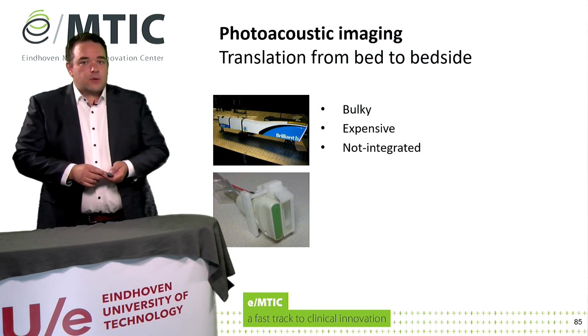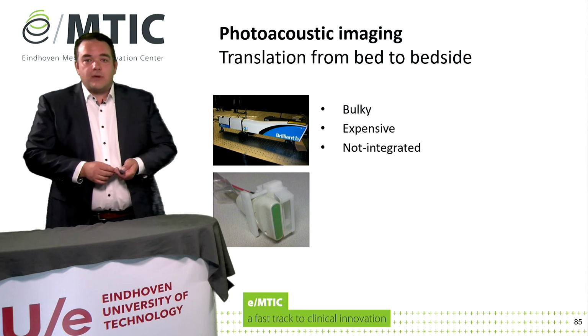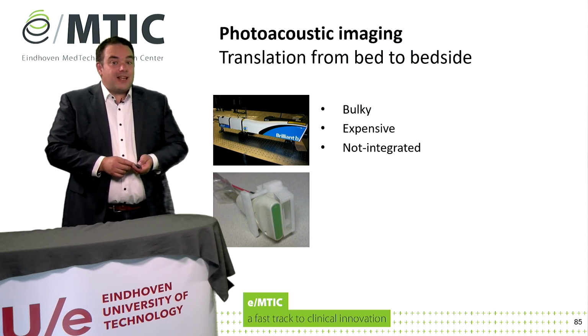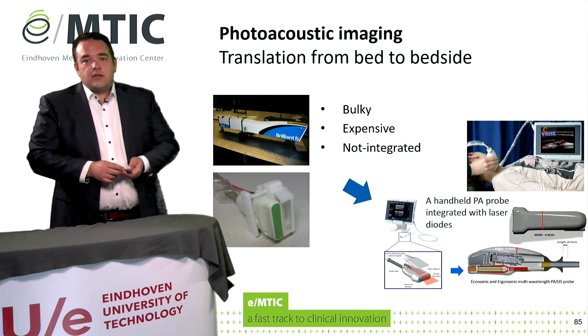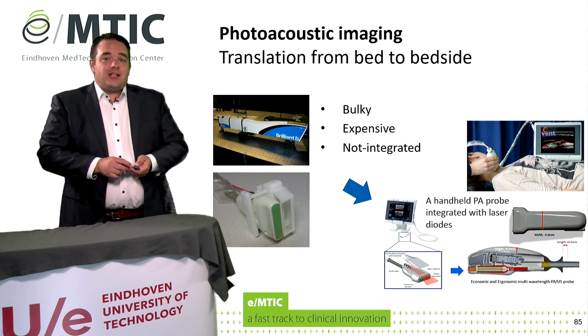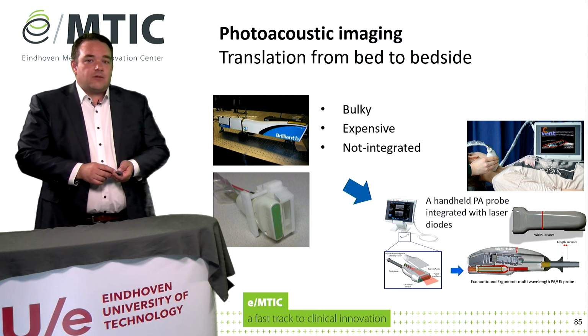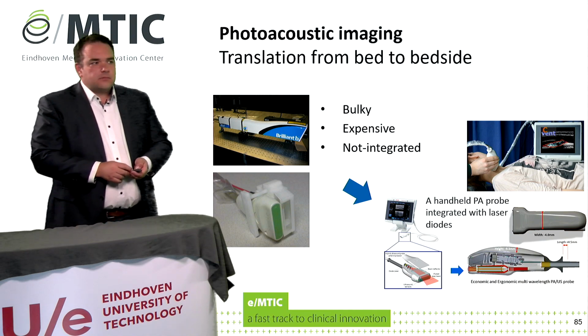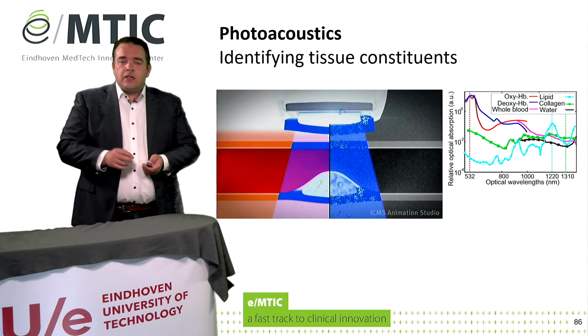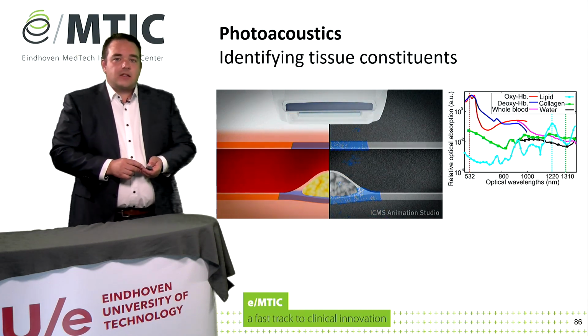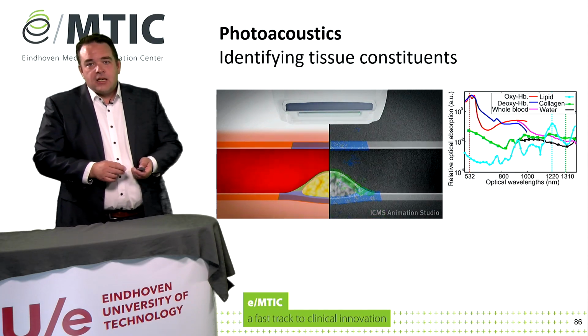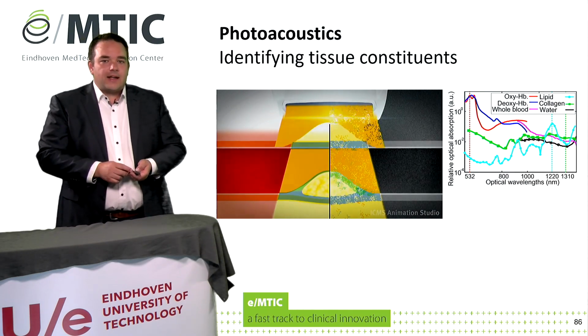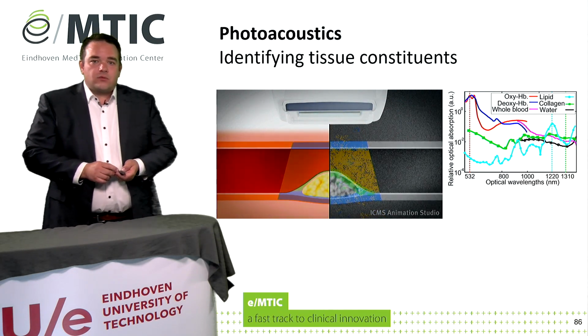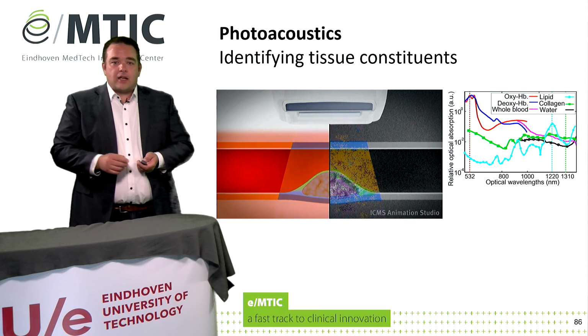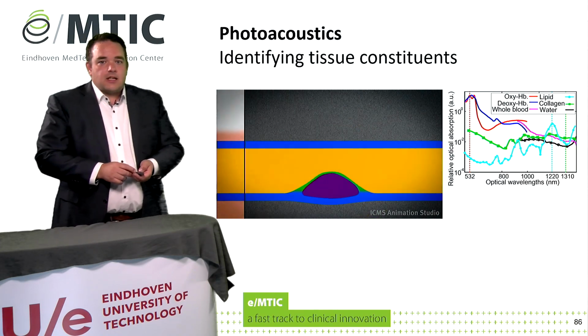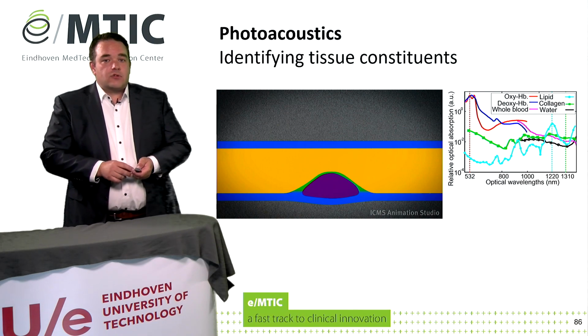However, to go into the clinic, where it's not widely applied yet, we need to get away from these bulky and expensive lasers that we typically use and are also typically not integrated with the ultrasound device. So recently we see a lot of developments where new handheld systems are being developed with the optics integrated with the ultrasonics. And when we have these devices and we choose our wavelengths of light wisely, we can actually perform non-invasive spectroscopy with photoacoustics. So we can send out different pulses with different wavelengths, get the received ultrasound that's generated because of the photoacoustic effect, and then distinguish between different tissue types, as is illustrated here quite basically in this animation on identifying the content of atherosclerotic plaques.